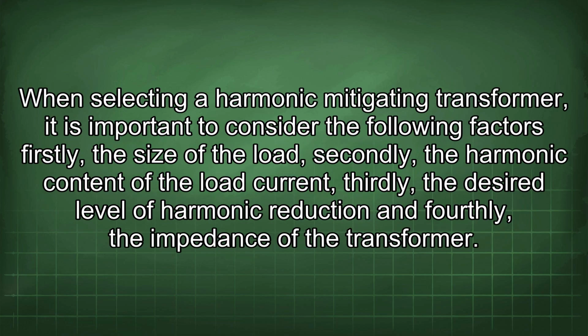When selecting a harmonic mitigating transformer, it is important to consider the following factors. Firstly, the size of the load. Secondly, the harmonic content of the load current. Thirdly, the desired level of harmonic reduction. And fourthly, the impedance of the transformer.